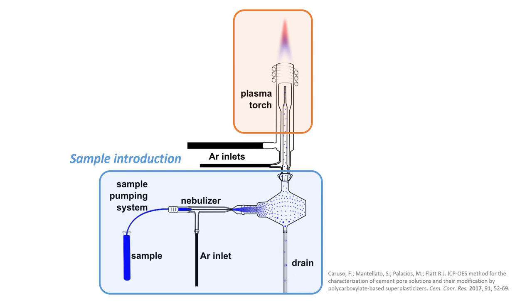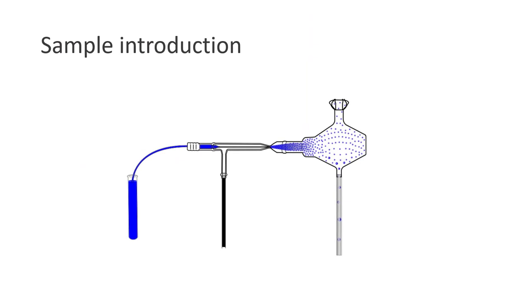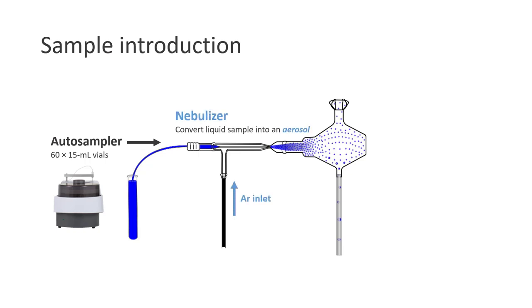First, let's take a look at the sample introduction system. In ICP, samples are introduced in a steady and continuous stream via an autosampler. The autosampler we will be using in this experiment can accommodate up to 60 samples at a time. A nebulizer then converts the liquid sample into an aerosol, which is a fine spray of droplets or mist.